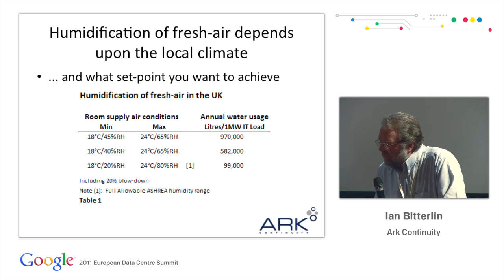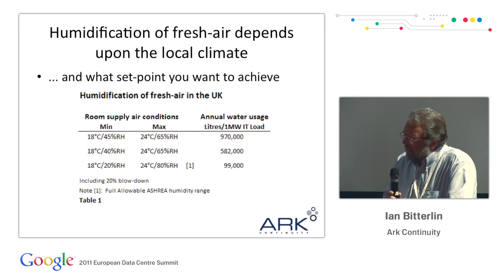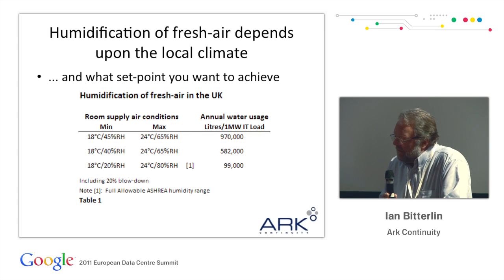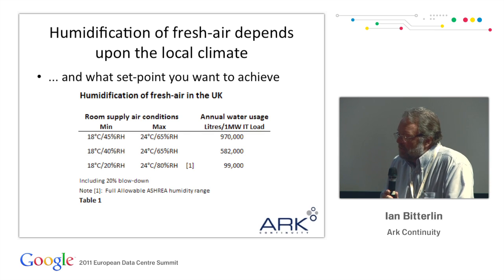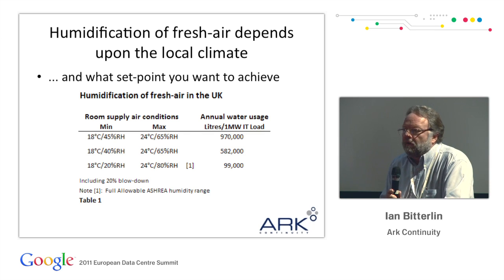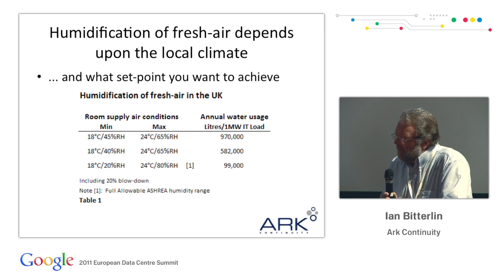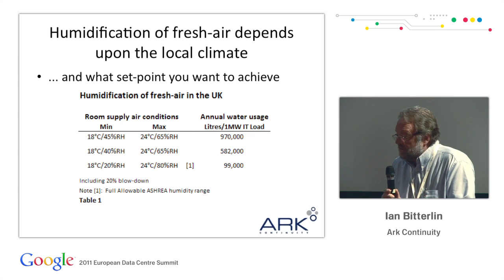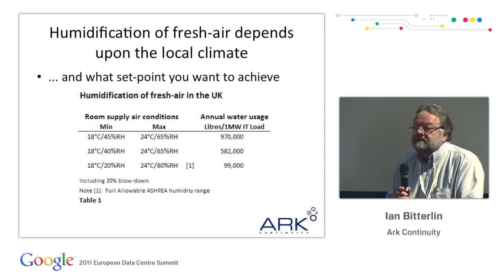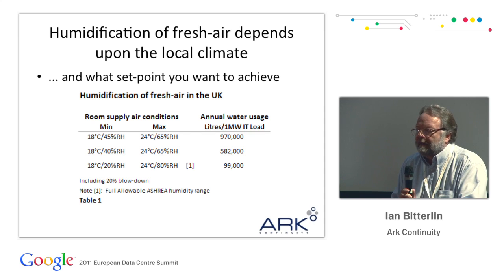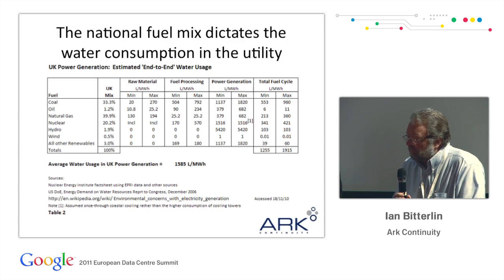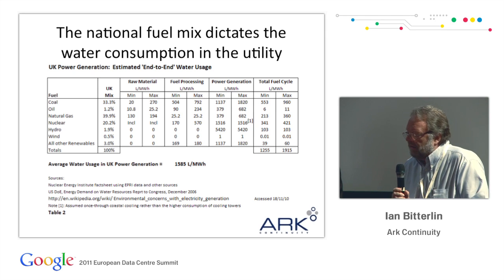So on here, I've put everything from a conventional 18 degree, 24 degree, 45 to 65 RH system. That's the system we're building currently, which needs nearly 1 million litres per megawatt per year. And right the way down to the ASHRAE allowable at the bottom. So 10% of that, if you allow your humidity to extend down to 20 and up to 80. Next slide. You can read these later, you certainly can't see them now.